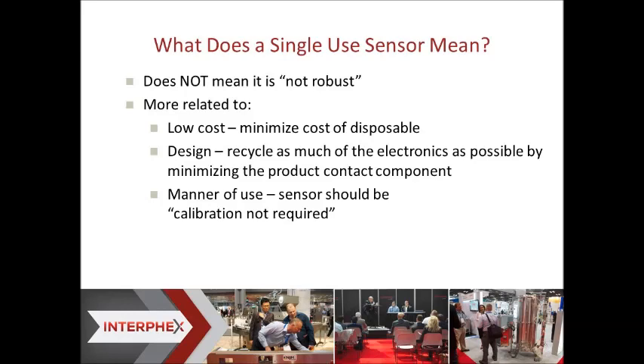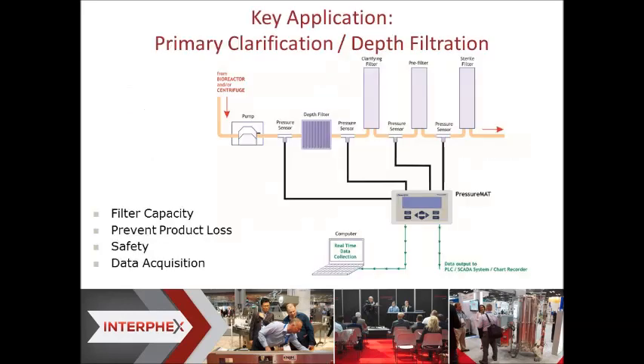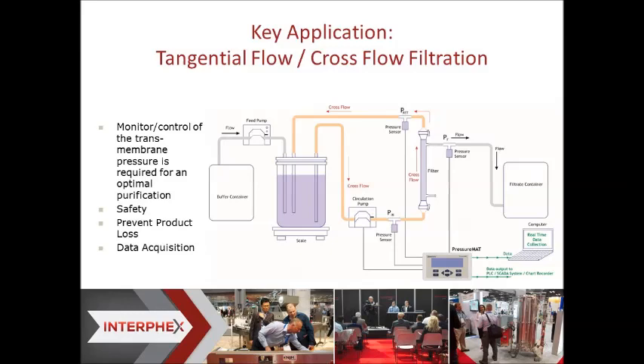And in order to implement the sensors to your process, you really want to have a sensor where calibration is not required. If you have to introduce standard solutions and buffers, etc., you're really going to take away a lot of the advantages of a single-use system. The key applications are in both upstream and downstream processing. Pretty much any application, you really want to measure pressure, which is described down here for both safety and to prevent product loss. And any sensor gives you the ability also to perform data acquisition. But in depth filtration, it also gives you the ability to measure your filter capacity and prevent breakthrough. In tangential flow filtration, particularly pressure measurements, important to measure and calculate the transmembrane pressure, which is the critical parameter required to measure the filter performance.